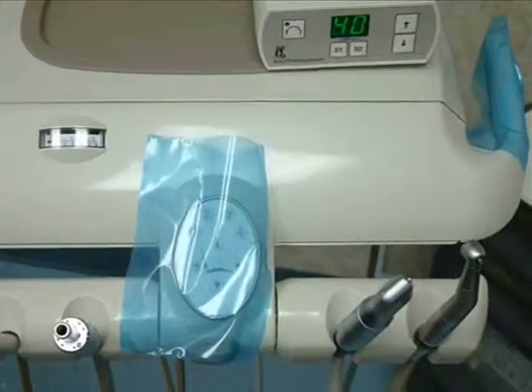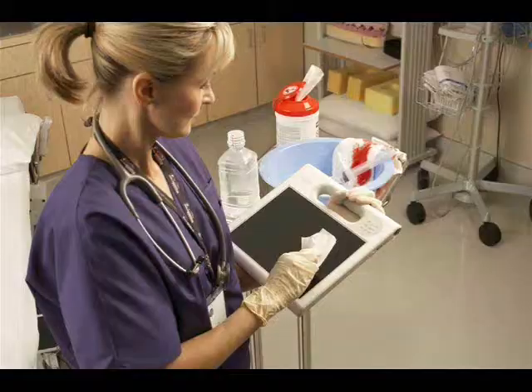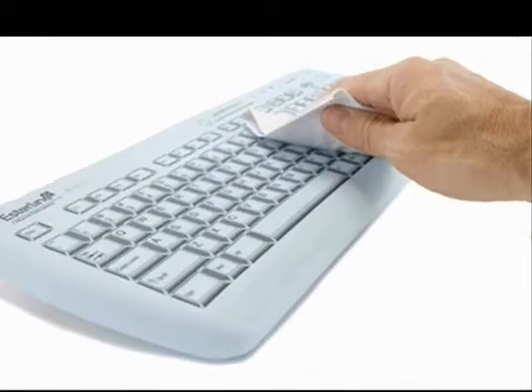The main advantage of virtual buttons on medical devices is that virtual buttons don't introduce any new cracks, crevices, or seams associated with the user interface. This means virtual buttons can be applied to any existing smooth, even curved surface so that you can very effectively sterilize the medical device. Other user interfaces — even membrane buttons, mechanical buttons, or touch screens — introduce cracks, seams, and crevices that are very difficult to sterilize with sterilization wipes or other methods.